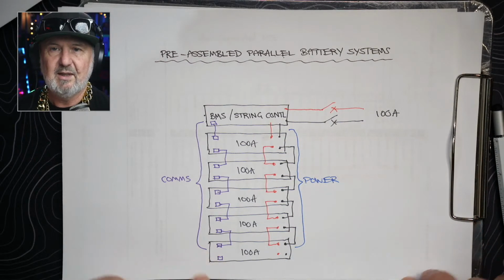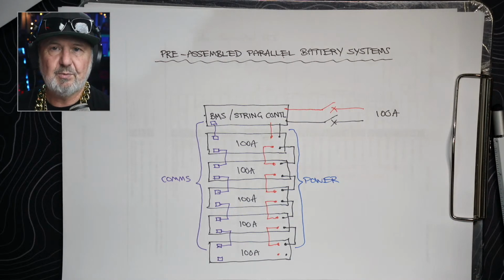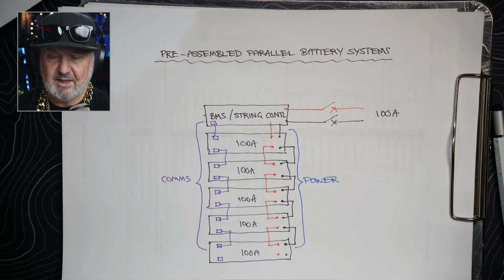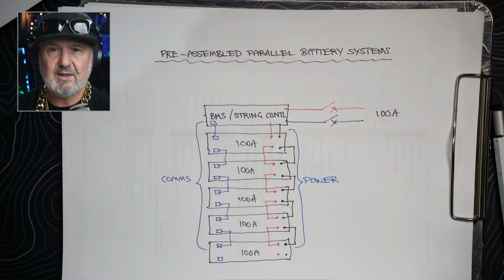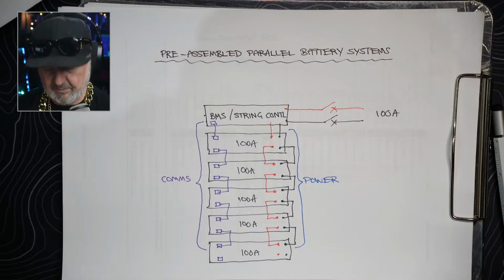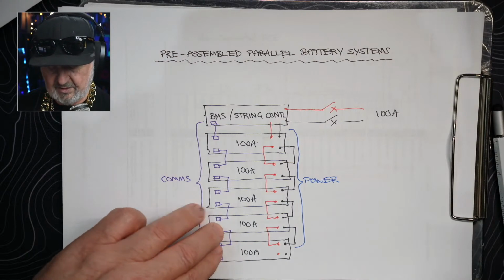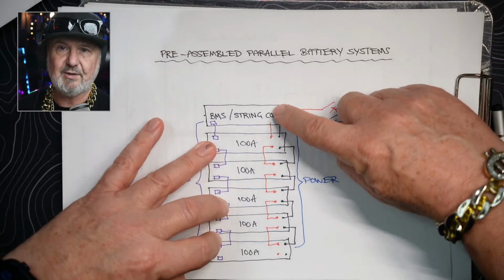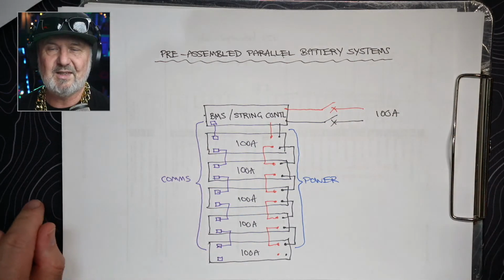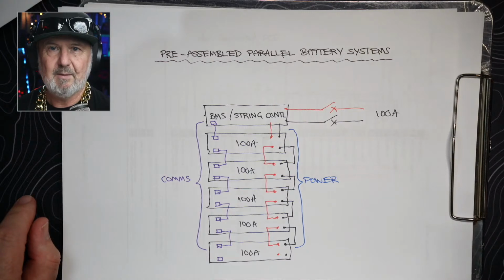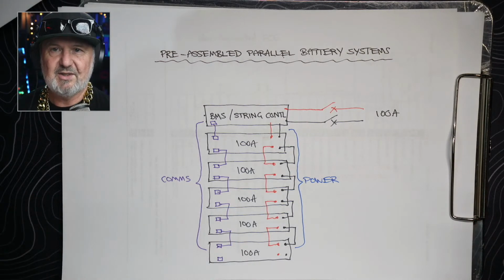every single battery module is, and can make sure that the current through all of the interconnecting cables stays within safe range. So if you're wondering why, for instance, when you look at the CEC approved module product list for batteries, just to give an example, because someone mentioned Pylontech, you'll see Pylontech are listed multiple times with 2 batteries plus controller, 3 batteries plus controller, 4 batteries plus controller, 5 batteries plus controller, because each one of those is a different pre-assembled battery system. And so they have to list them all individually.